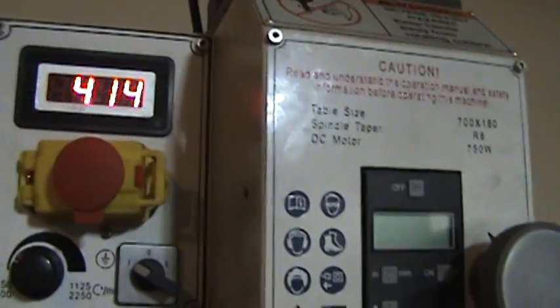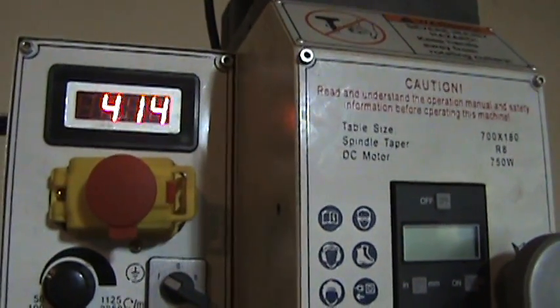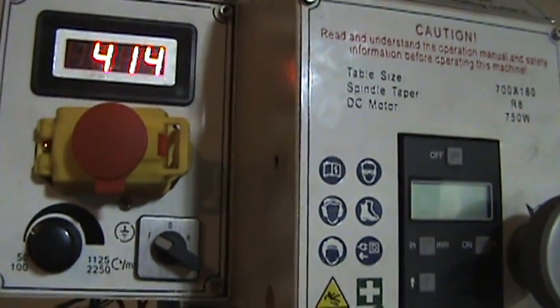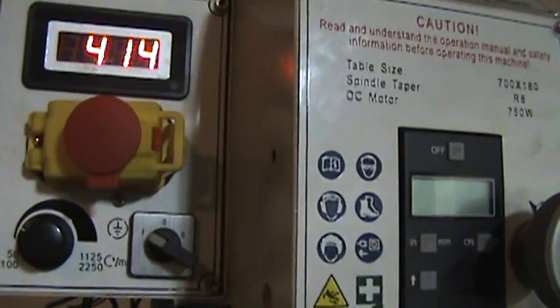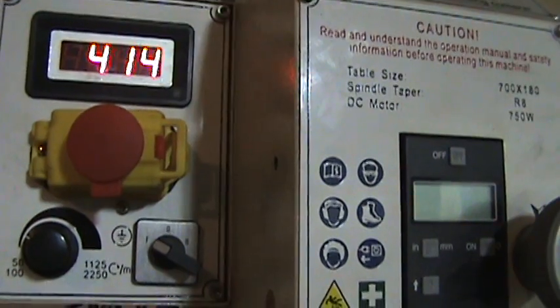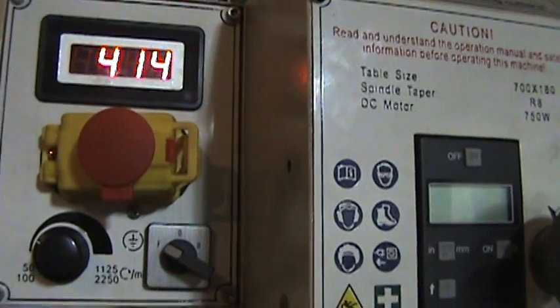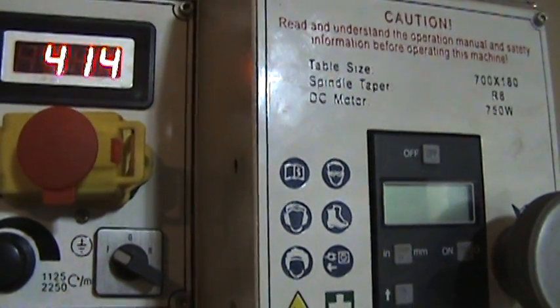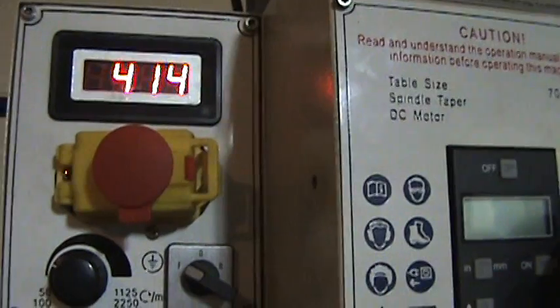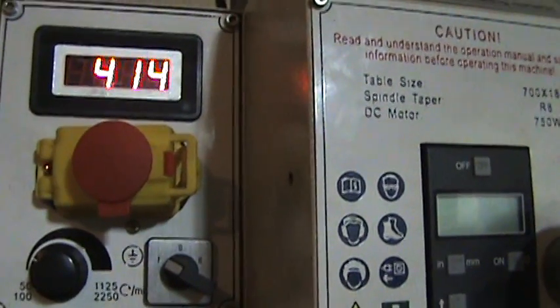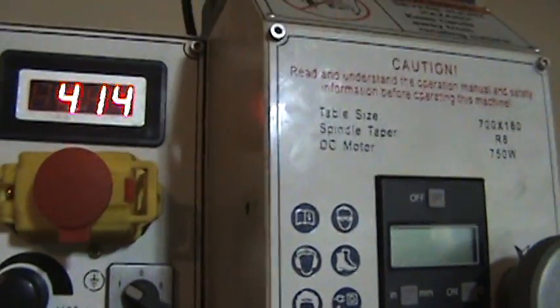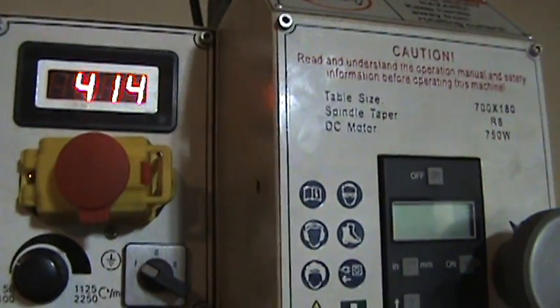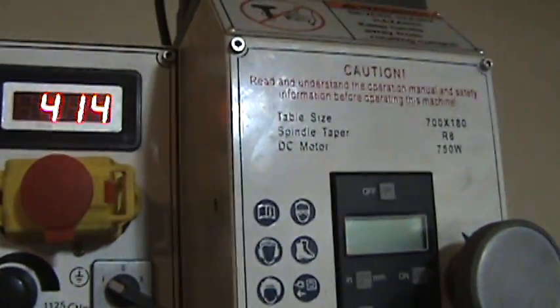But I've got it turned back up almost all the way, and I've got the current limit set about what I'm guessing is about 175% of the motor rating. It says don't ever turn it over 200%. So the best I can tell, I've got everything set okay, but I don't know how to fix this.